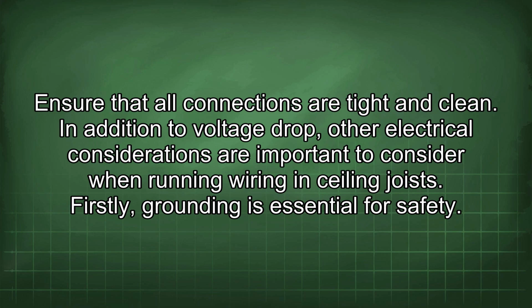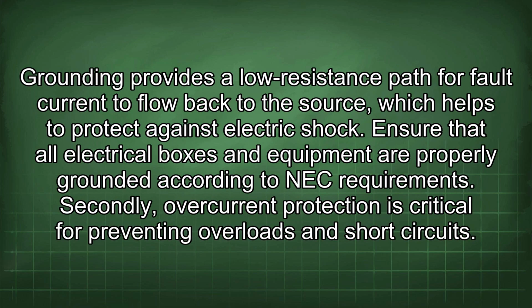In addition to voltage drop, other electrical considerations are important to consider when running wiring in ceiling joists. Firstly, grounding is essential for safety. Grounding provides a low resistance path for fault current to flow back to the source, which helps to protect against electric shock. Ensure that all electrical boxes and equipment are properly grounded according to NEC requirements.